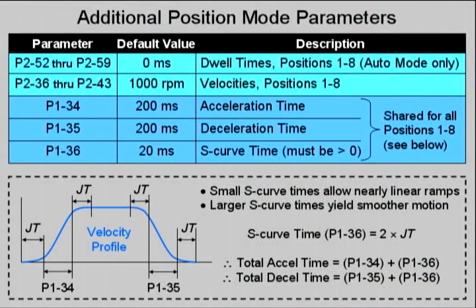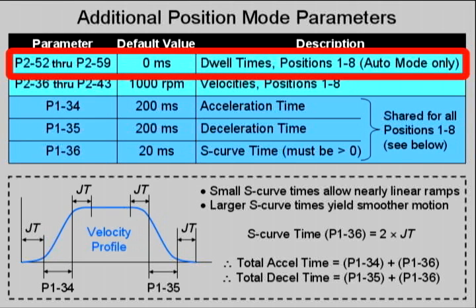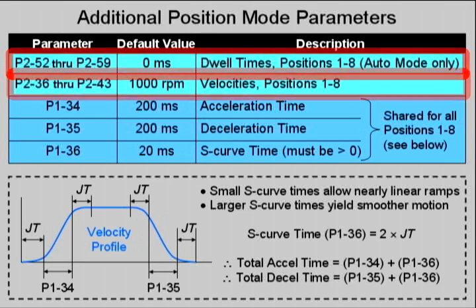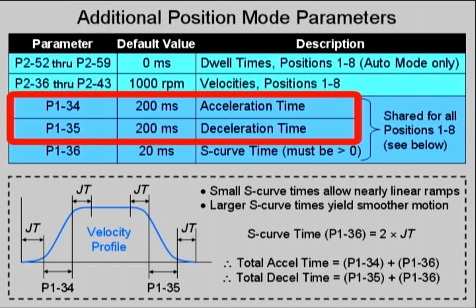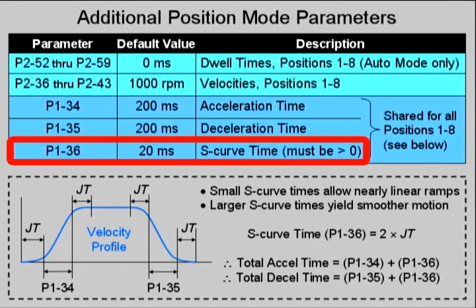The SureServo also supports automatic positioning with either absolute or relative moves, with preset dwell times for each position. In this entire example, we've been using the default speed and acceleration values in the drive. The SureServo allows a separate velocity value for each of the eight moves. Separate acceleration and deceleration values are shared for all the moves. The drive even supports S-curve acceleration and deceleration for smooth starts and stops. See parameter P136 for more information.